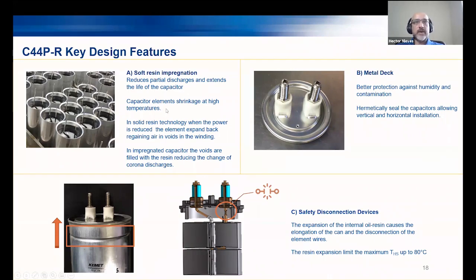So imagine, for example, you have an AC filter capacitor that is solid resin, and then this capacitor starts to overheat. What is going to happen is that the polypropylene material starts shrinking, and then it basically starts releasing air surrounding the winding of the element. But at some point, when this capacitor returns to the normal stability of lower temperature, the polypropylene starts to expand again to its normal condition. So it starts absorbing the air surrounding the capacitor. That air surrounding the capacitor is what can create corona, and it is air with humidity.